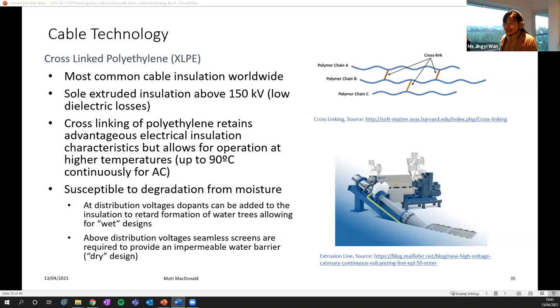It is susceptible to degradation from moisture. At distribution voltage, the solution is to add dopants to the insulation to retard the formation of water trees, which then allows for so-called wet designs. Above distribution voltage, seamless screens are required to provide an impermeable water barrier. This is called a dry design.